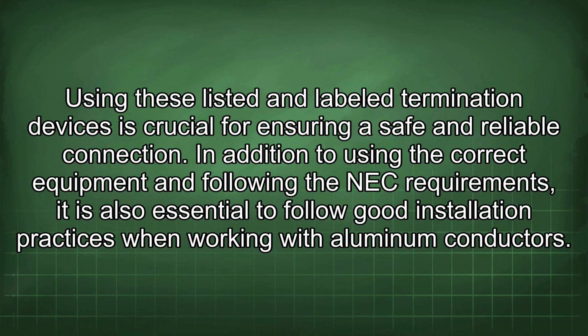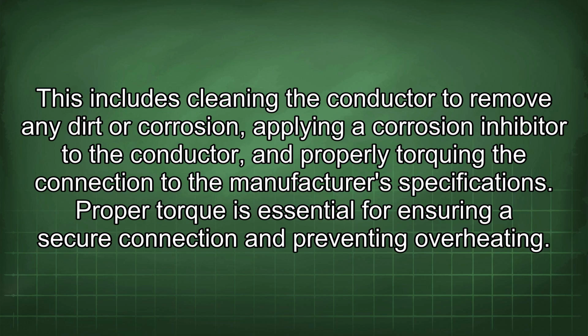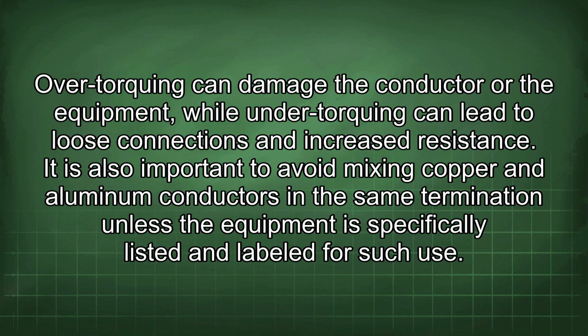In addition to using the correct equipment and following the NEC requirements, it is also essential to follow good installation practices when working with aluminum conductors. This includes cleaning the conductor to remove any dirt or corrosion, applying a corrosion inhibitor to the conductor, and properly torquing the connection to the manufacturer's specifications. Proper torque is essential for ensuring a secure connection and preventing overheating. Over-torquing can damage the conductor or the equipment, while under-torquing can lead to loose connections and increased resistance.